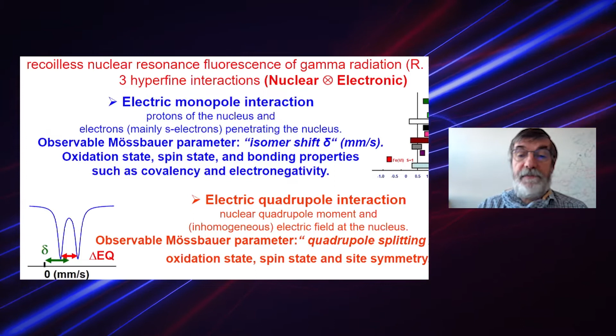So sometimes it's very important to apply an external magnetic field. The first point is to check that the source is not polarized. Typically here, as you can see, we have some compensating coils, where the field is opposite to the leakage field, and we are sure that the source is not polarized.